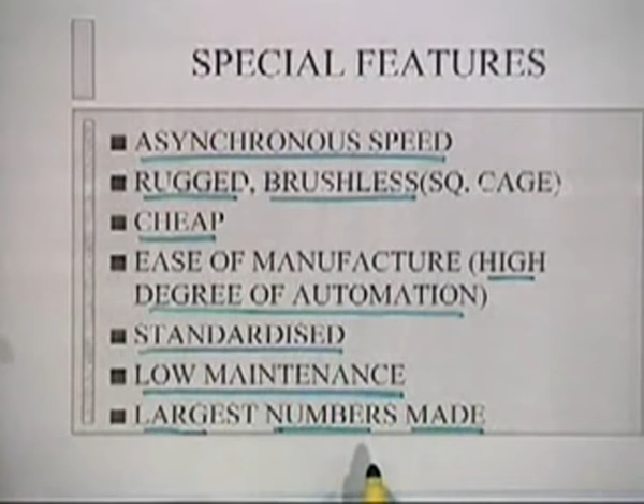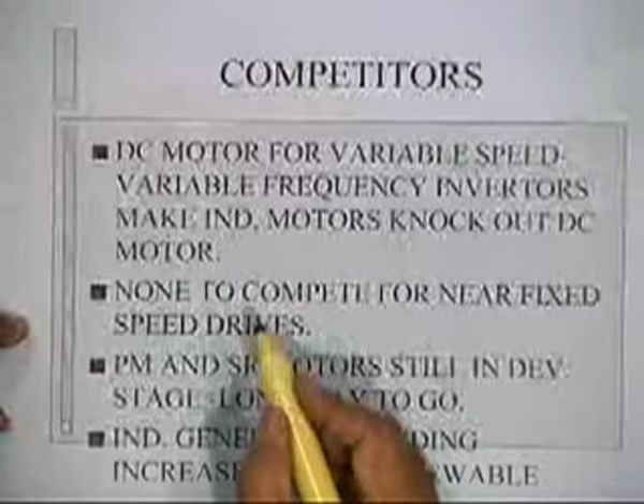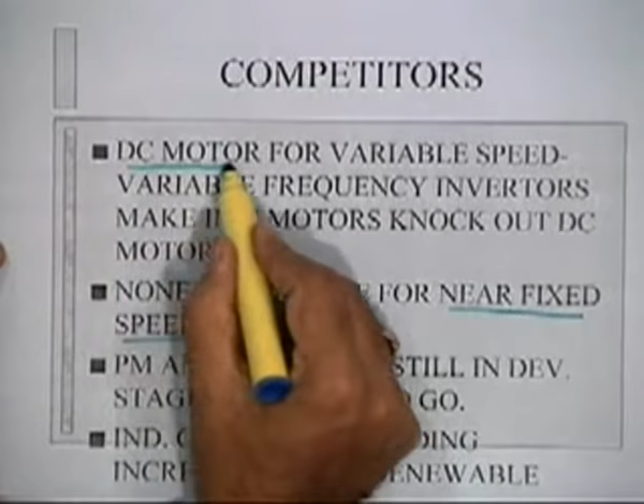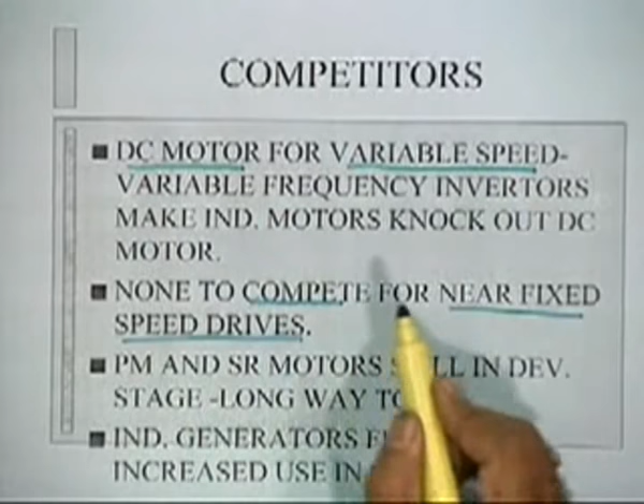Now, who are their competitors? One has to look at the competitors for three-phase induction motors and why the other competitors are getting knocked out. There is no competitor for near fixed speed drives till today. Wherever you need a near constant speed with a very marginal change in load, induction motors are the solution. But one can question whether it is suitable for variable speed, because DC motors have been for years or decades preferred for variable speed applications, because of that versatile commutator which makes it suitable for independent control of voltage and flux, and that makes it a very good variable speed device.